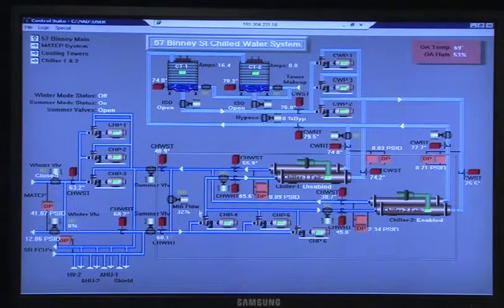So these pumps are circulating the chill water through here, down to our air handlers, down to all of our equipment, back up the building, through our pumps, and through the chiller. So that's how it's looping. And when we change it over, you should see everything change over automation-wise. You see all these statuses change. These open, these close, isolate our chiller. Everything shuts down over here automatically.